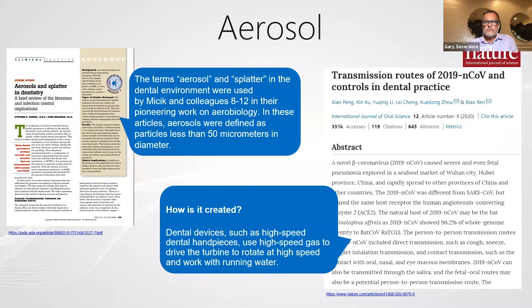But we make a distinction based on surgical masks and also respirators that splatter, usually a larger particle, and they say it is more like a ballistic, meaning it goes a little bit but drops fast. Aerosol, which we know can stay in the air up to 3 hours now, we need to move that out if we can. And we do that with air management systems, right? So we can put fans in place, we can look at our HVAC systems and try to get all the aerosol out of the breathing zone and onto surfaces, floors where we can use disinfectants, or we can get it out or recycle or recirculate that air. So that's pretty interesting to look at too.